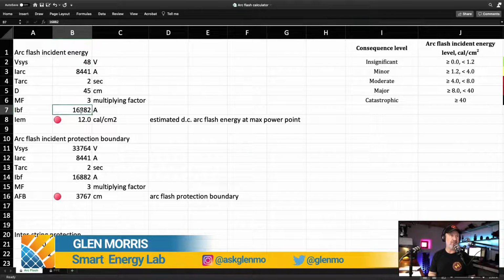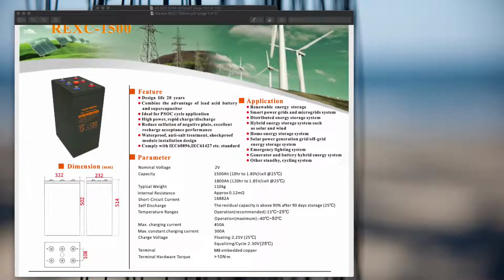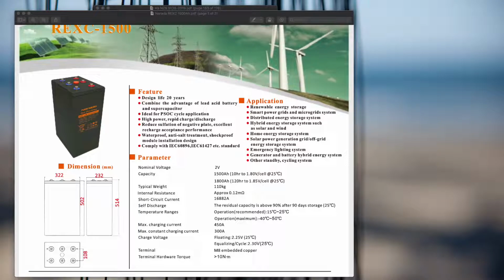Now, how do you come up with the bolted fault current? You need to find out from the manufacturer what this is. So I'm just going to go over to another screen. Here we go. This is a data sheet for a sealed lead acid 1500 amp hour battery. Oops, just bring myself up here. Got the wrong person. And there is the specification of that system. So it's 1500 amp hour, at the 10-hour rate at 25 degrees Celsius, and a little bit further down it says internal resistance is 0.12 milliohms per cell, and the short circuit current is 16,882 amps. That number there is actually what we're after.